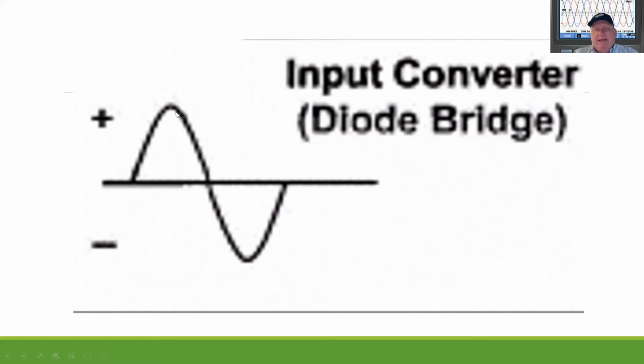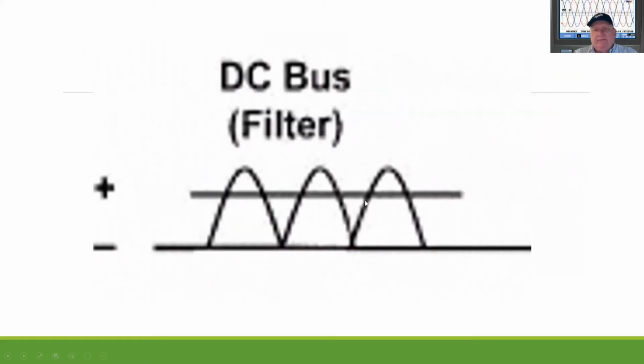So again, we have the AC coming in, feeding from the diodes, which creates this DC bus circuit. Then from the DC bus, it creates PWM with IGBT transistors that are all these pulses. And you'll hear things like carrier frequency. That means how many pulses per second they're giving. Some of them now are as high as 15,000 pulses digitally firing per second. So it ends up being what they call high frequency switching.